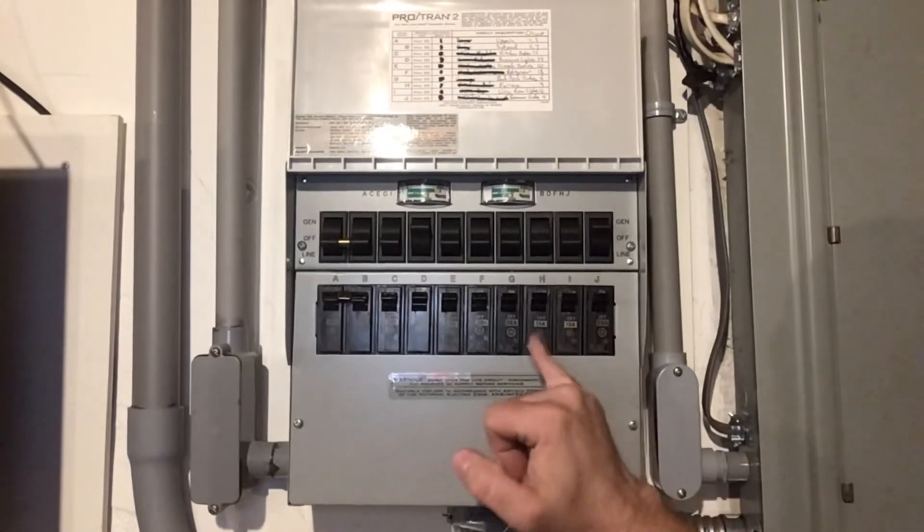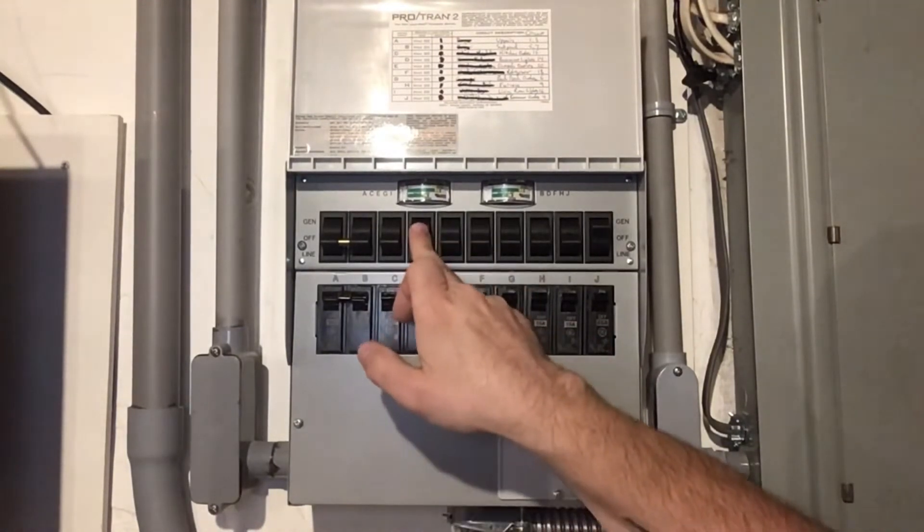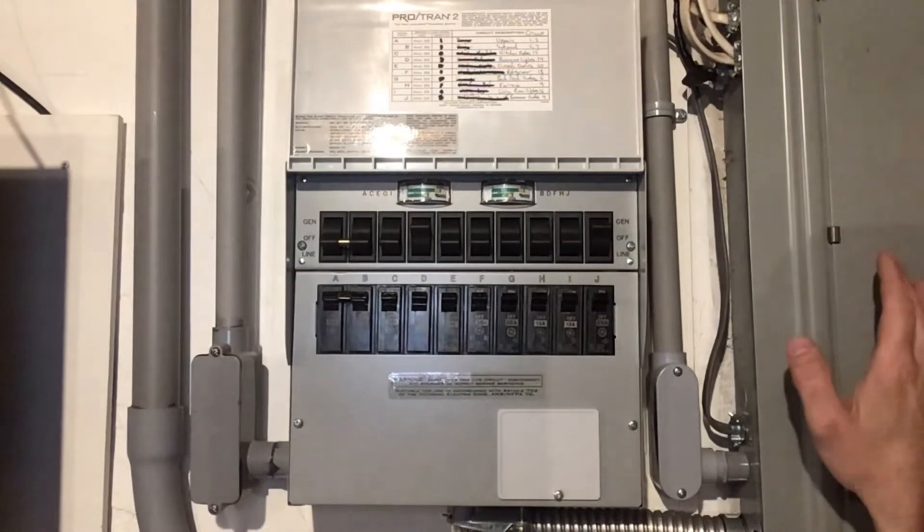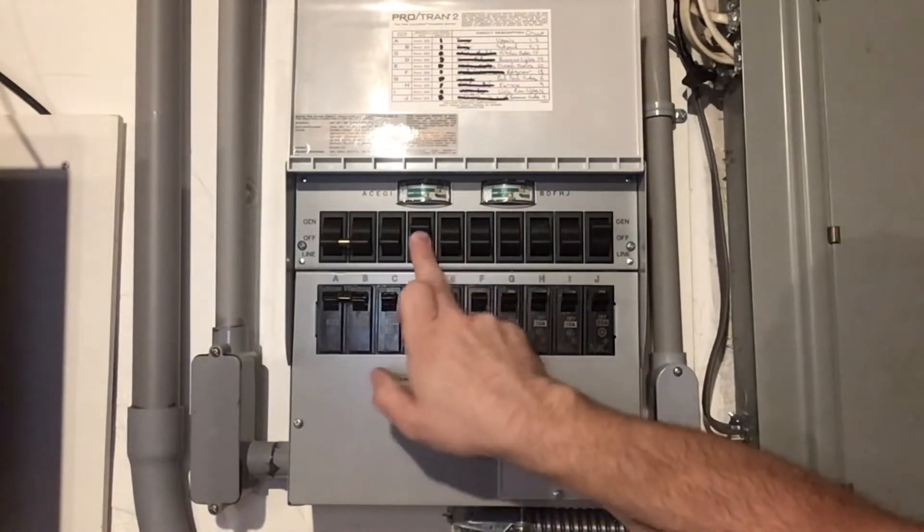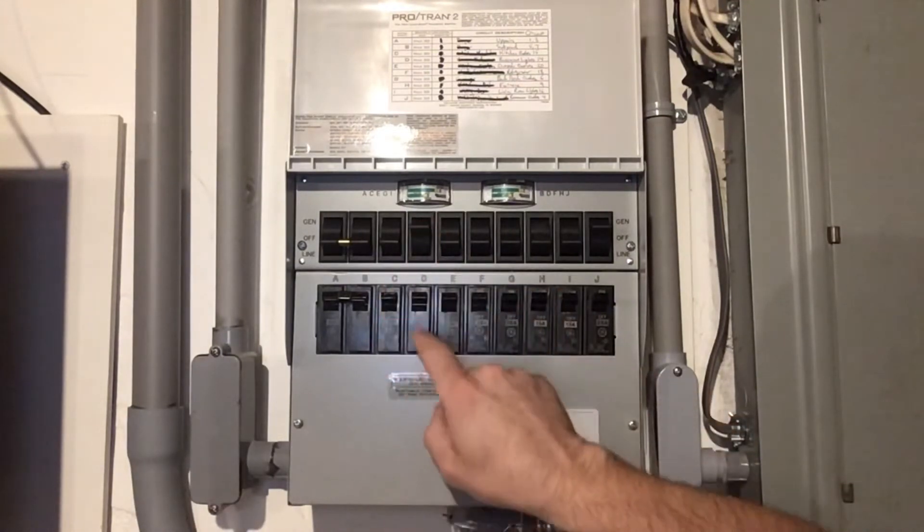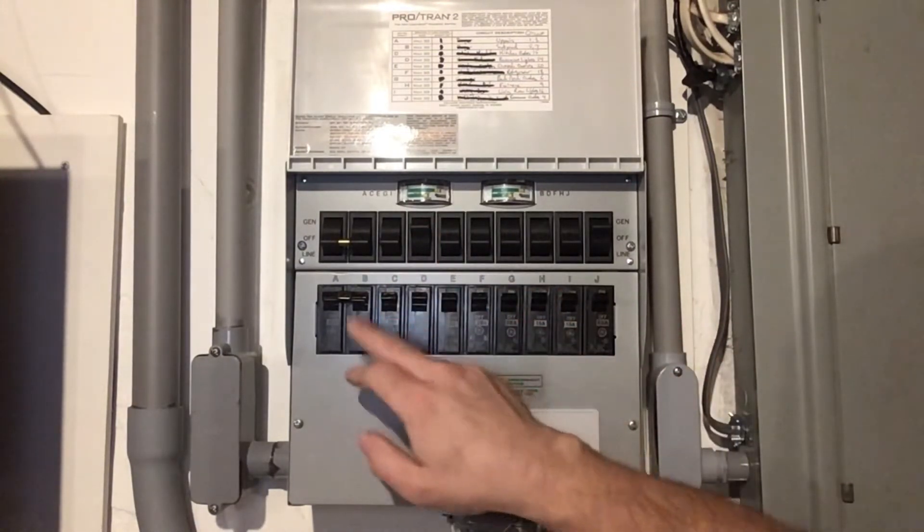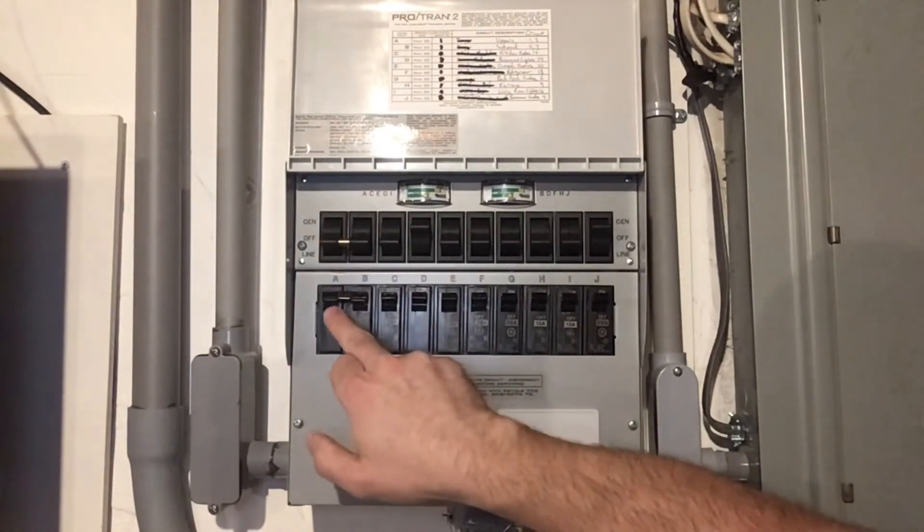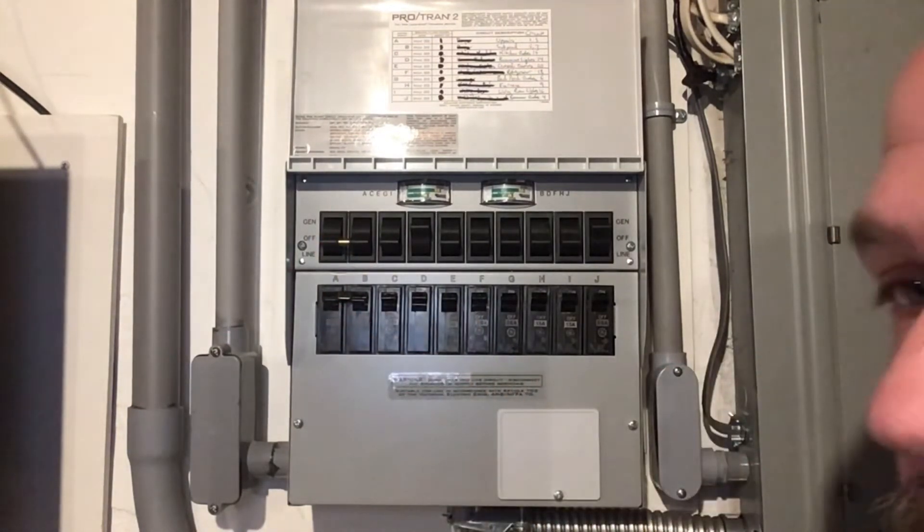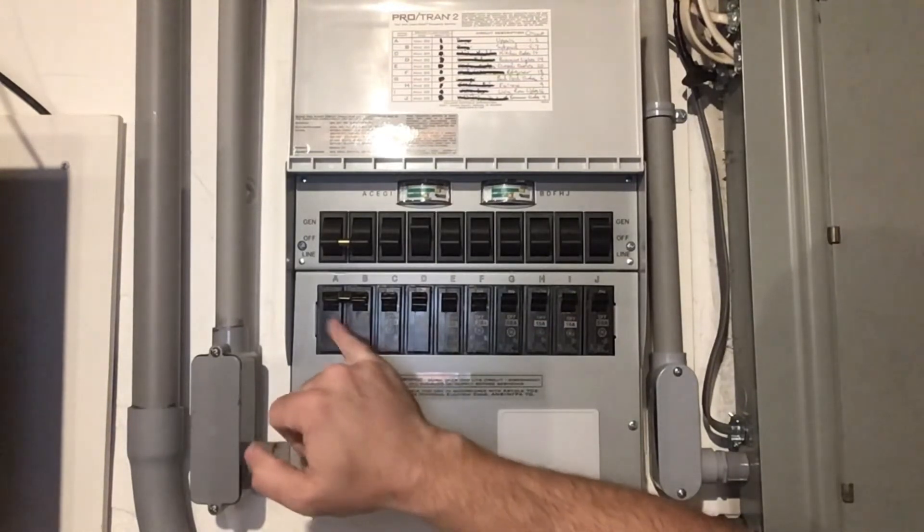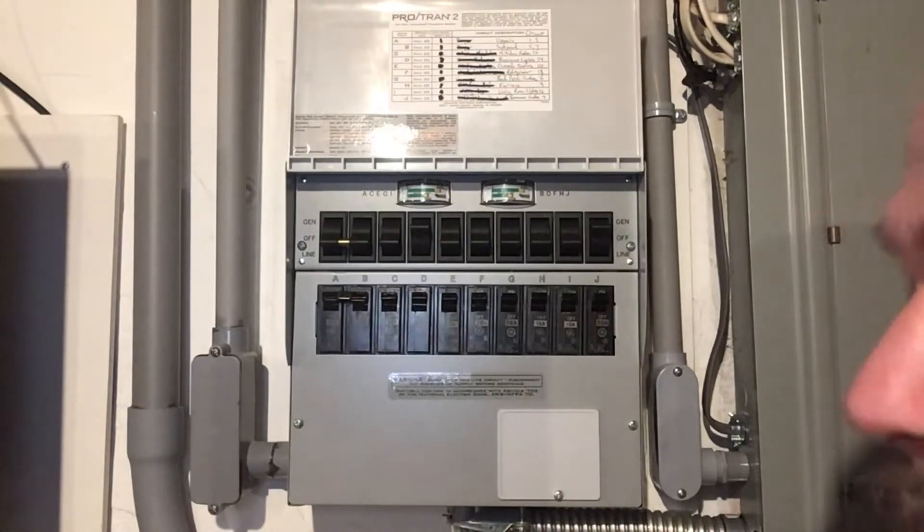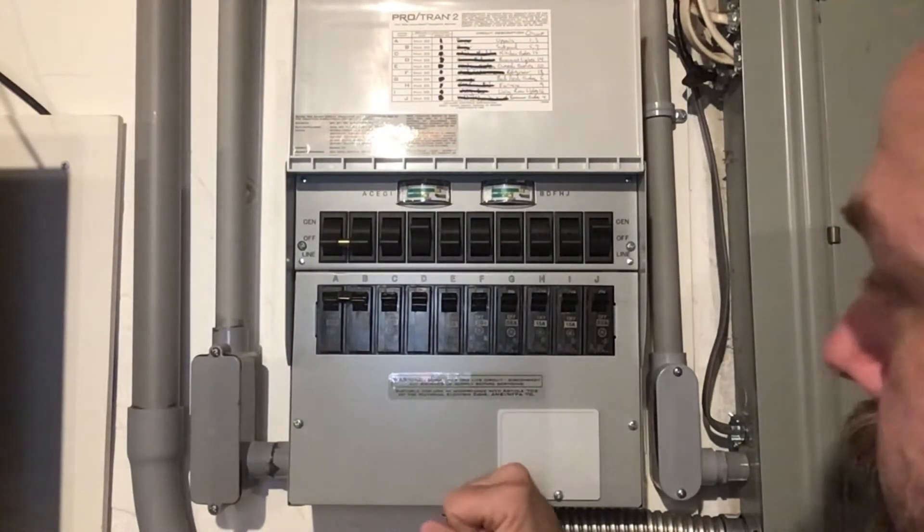You can see each of these circuits also has its own breaker. So when we switch it to generator, it bypasses the breaker in the main panel and this becomes the breaker. So if we have this switch, this is the basement lights. If for some reason that becomes overloaded, it's going to trip this breaker, not the one in the panel. Over here, you can see we have a 240 volt 30 amp circuit. Our house actually has a sub panel in the upstairs. So that one paired circuit can power the entire upstairs, all three bedrooms and the bathroom in our house. That's just the way our house is wired. It's kind of convenient for this sort of thing.